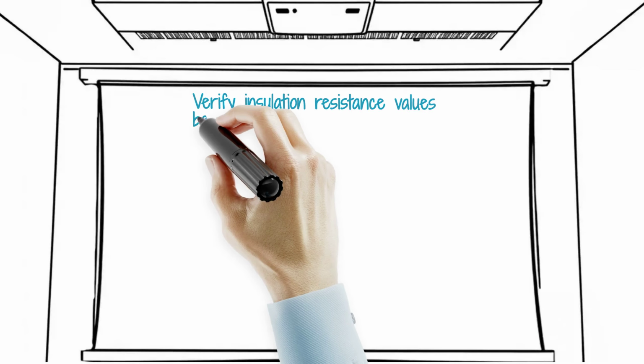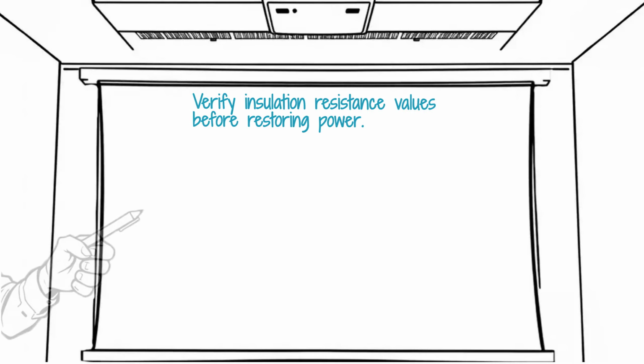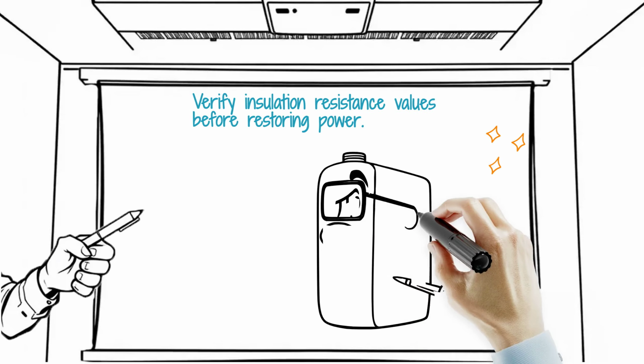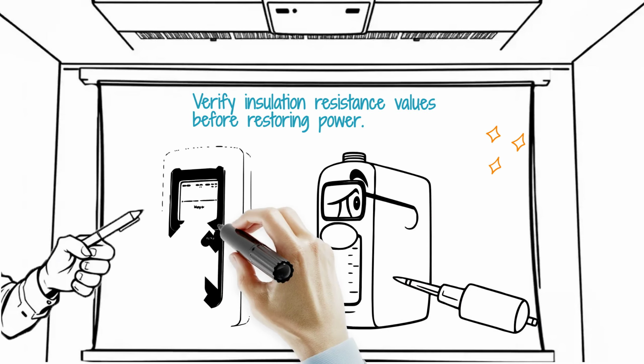Insulation resistance tests, or Megger tests, must be performed on all windings and circuits. The insulation resistance values must be well within acceptable limits before any attempt is made to restore power.